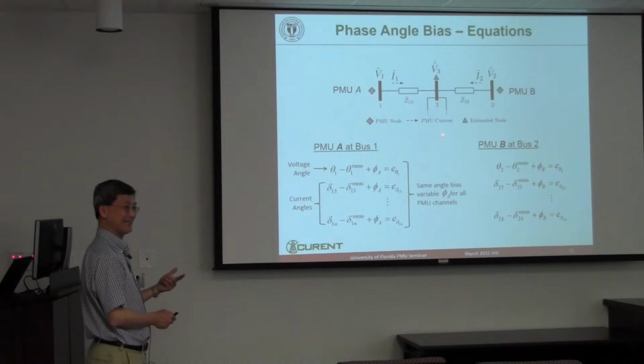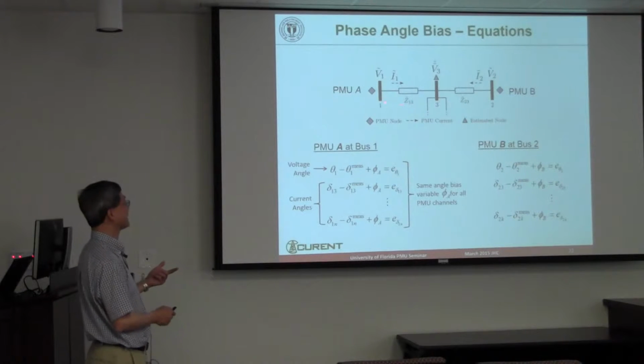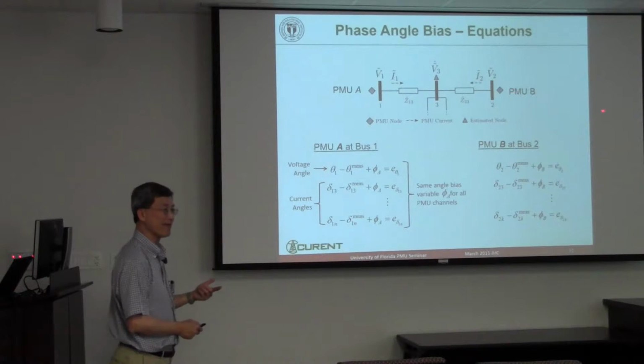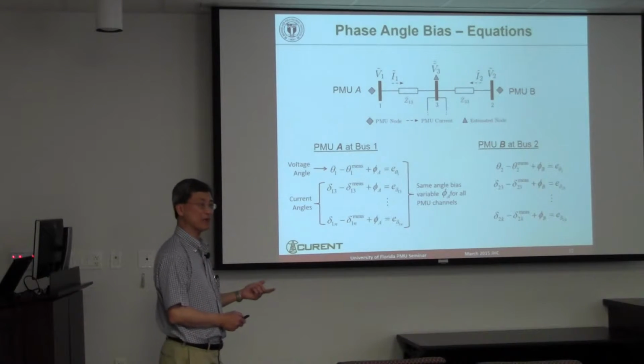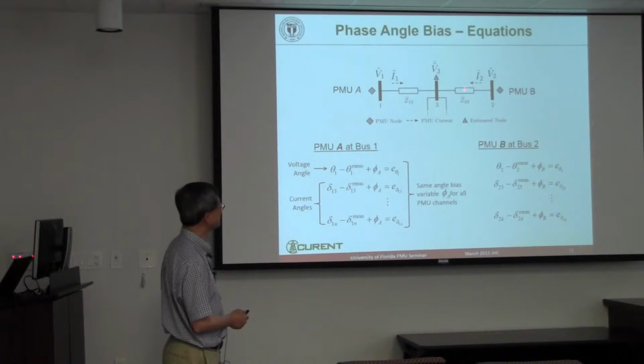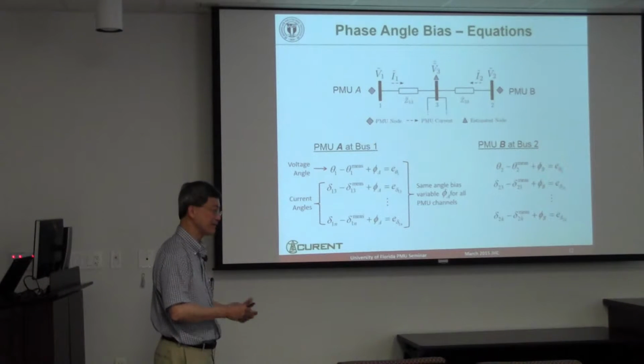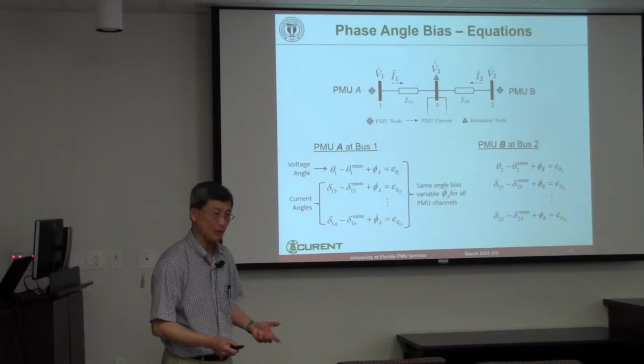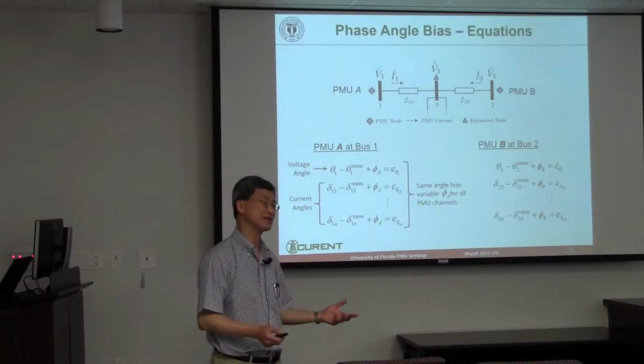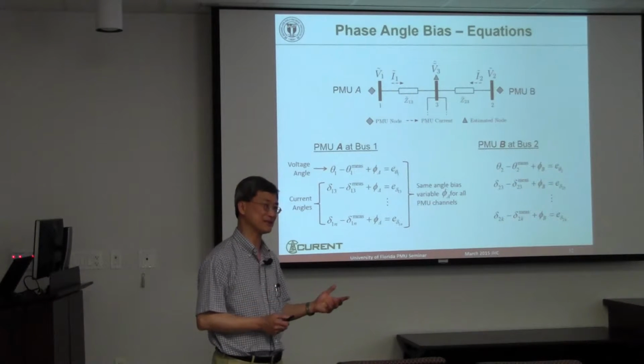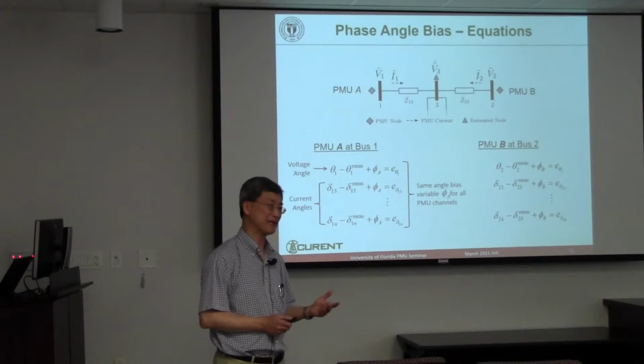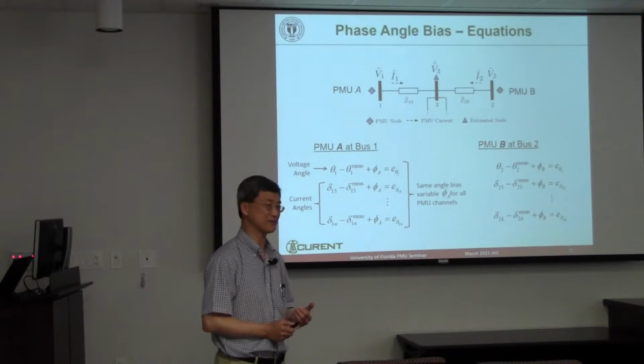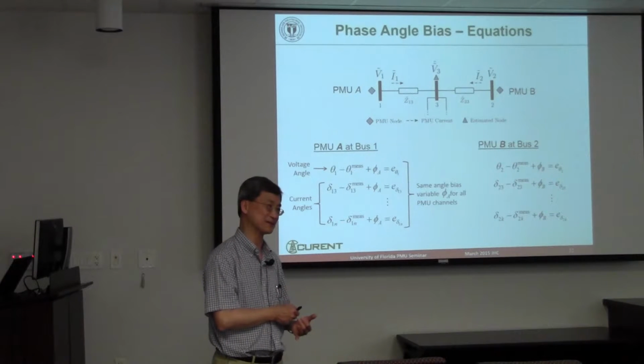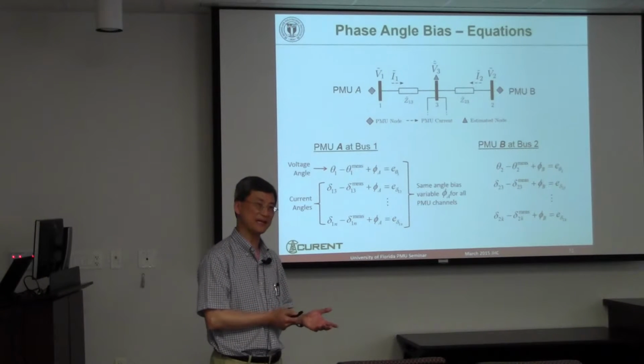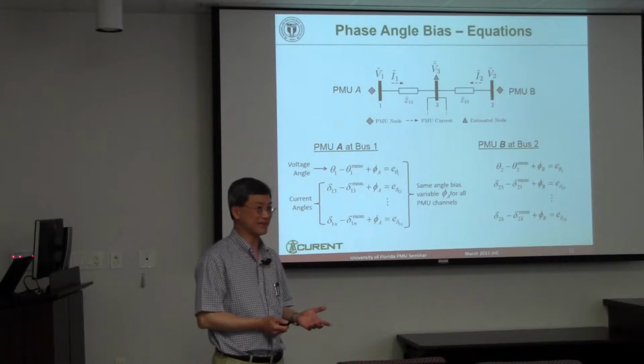Do you really know the reactance? Yeah, the reactances are actually quite good. We're now at a point where, at the very end, we were looking at about 1% error in the adjusted phasor data. That 1% error could truly be due to inaccuracy in the phasor, or in the line parameters, but once you get down to 1%, it's difficult to correct further.